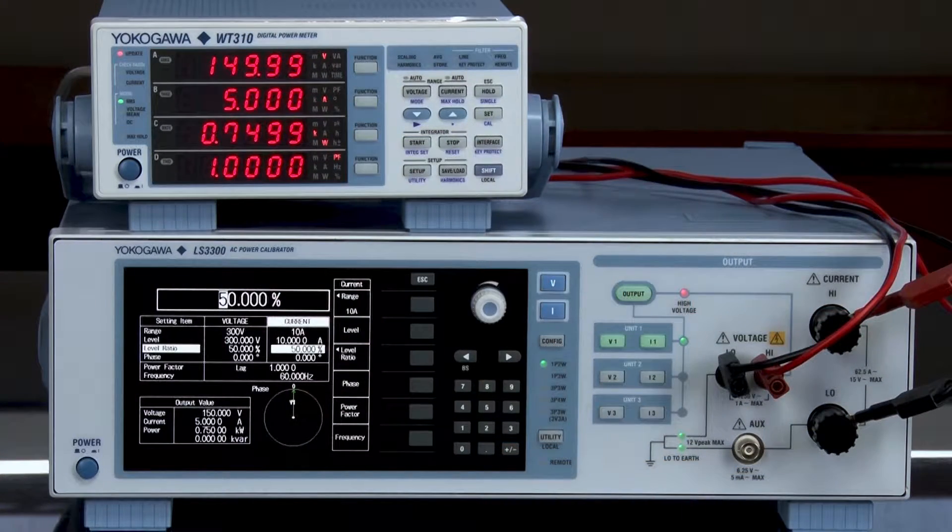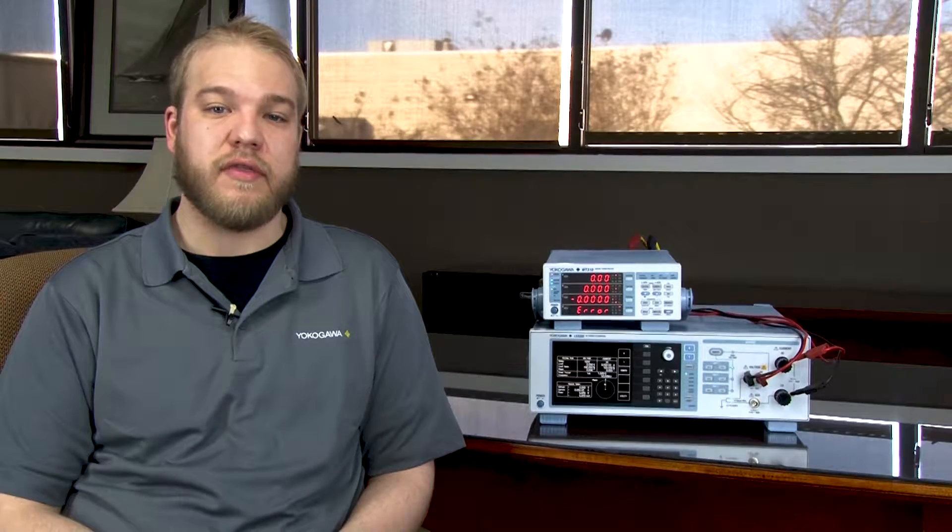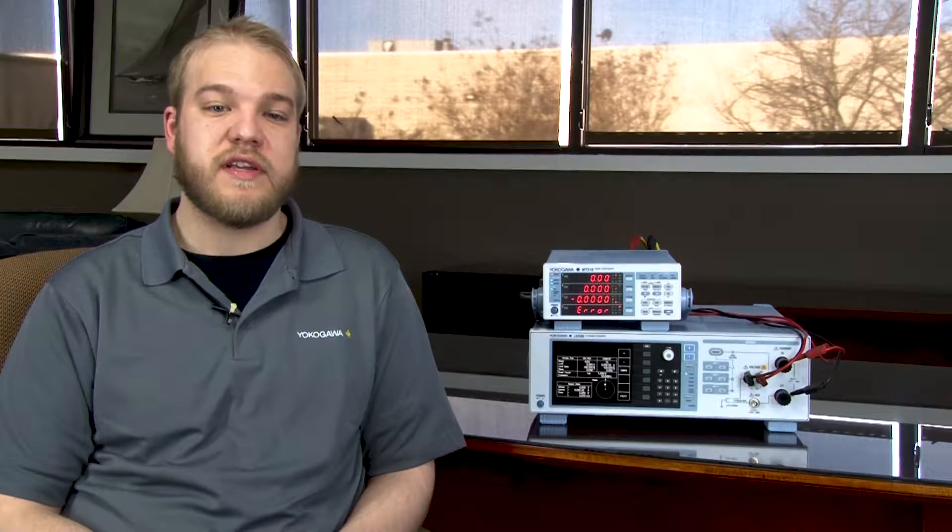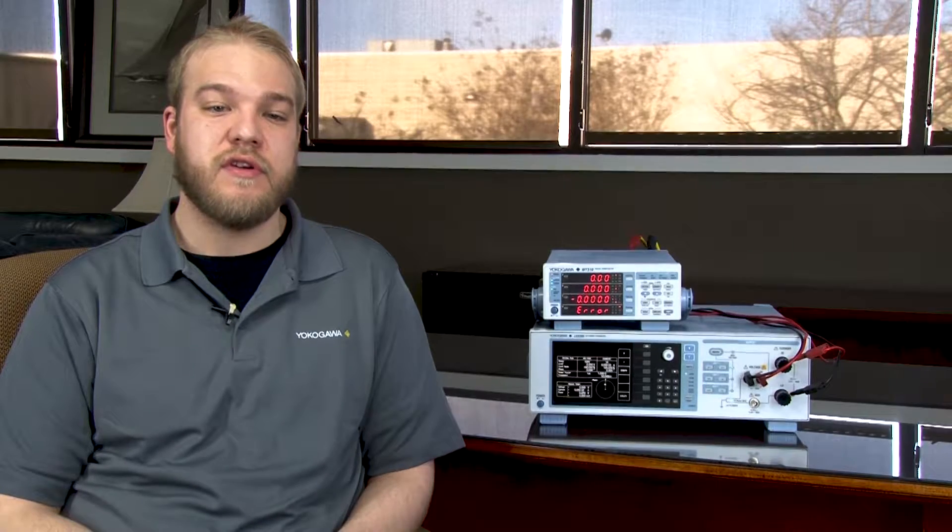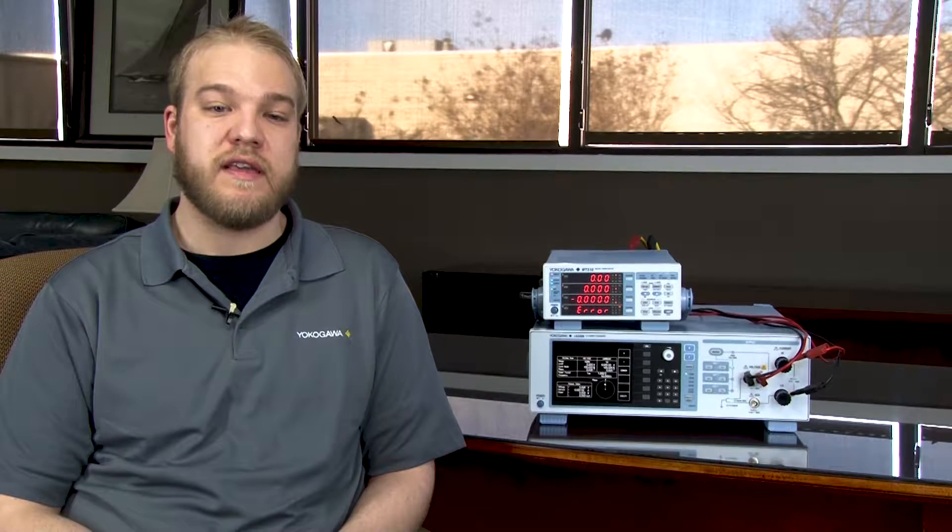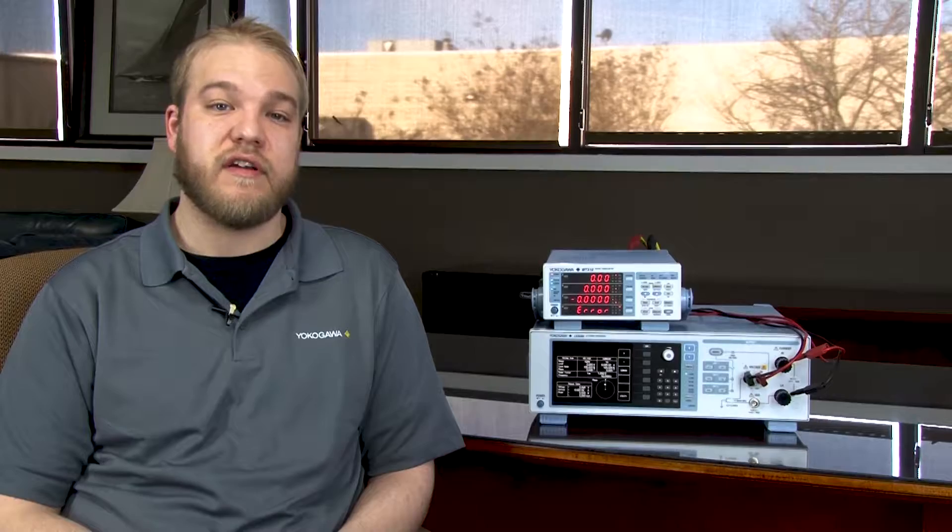I will be testing one input element using the one phase two wire method, although this approach is applicable to a three phase three wire or three phase four wire method if multiple LS3300s are used. This performance test I will demonstrate provides test accuracy ratios for current and voltage of the WT300 and 300E series as well as accuracy verification.